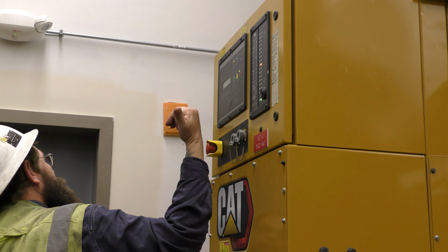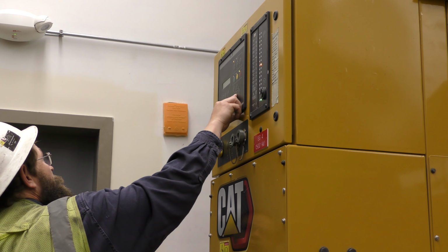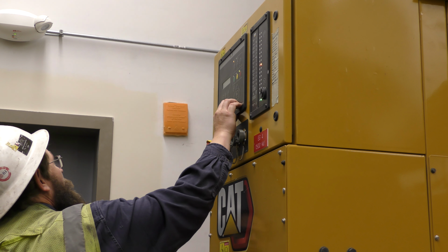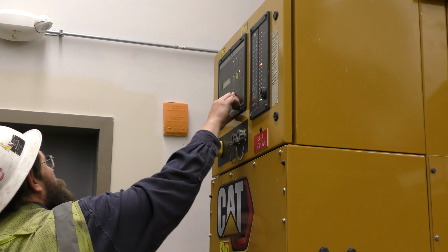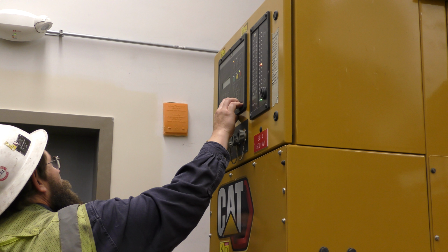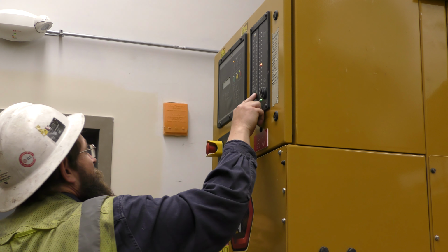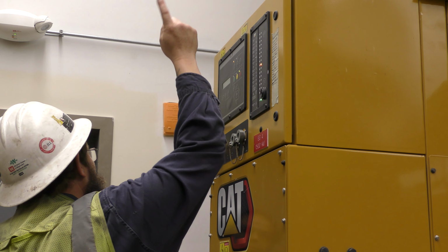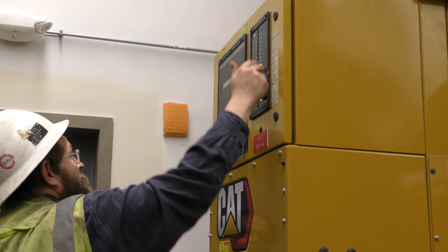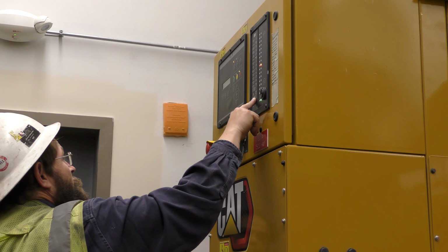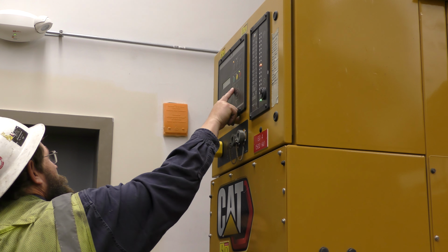If you have an engine warning that's not displayed on these set parameters, go down to your engine control and it'll tell you what the engine ECU is telling you is wrong with it. And there's the DIO module, which will tell you the same thing. This is an external module, that's where we're getting our low coolant temperature and low coolant level alarms coming into. Those will display here. Your rupture basin and critical low fuel will display here. They're also in there.